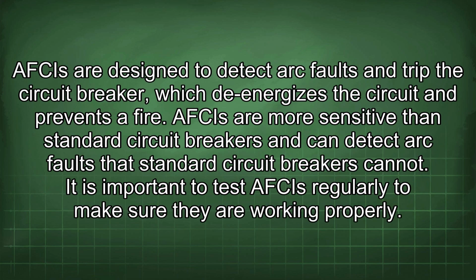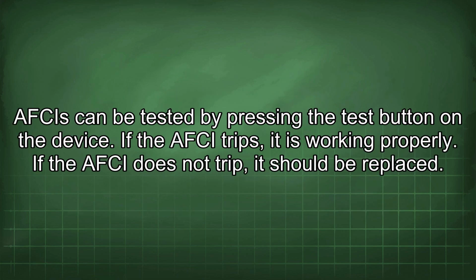AFCIs are designed to detect arc faults and trip the circuit breaker, which de-energizes the circuit and prevents a fire. AFCIs are more sensitive than standard circuit breakers and can detect arc faults that standard circuit breakers cannot. It is important to test AFCIs regularly to make sure they are working properly. AFCIs can be tested by pressing the test button on the device. If the AFCI trips, it is working properly. If the AFCI does not trip, it should be replaced.